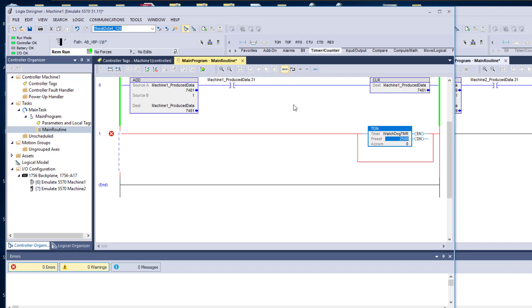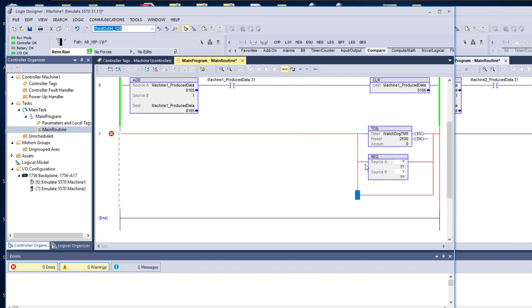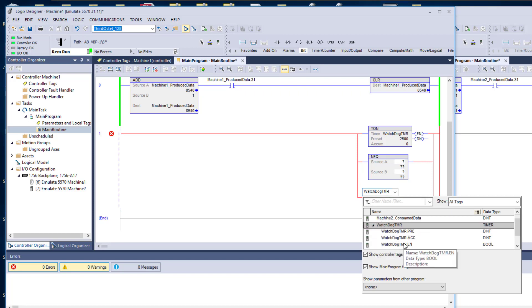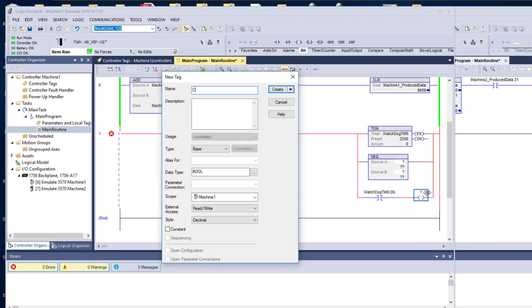Now what we want to do is actually get the data from here. We're going to do a compare and say not equal to. We'll add another rung down here and use this as the done bit. If this watchdog timer goes done, then we want to say that there is a comms fault — at that point we'll just make a bit that says comm fault. So if the watchdog timer finishes, that's what happens.